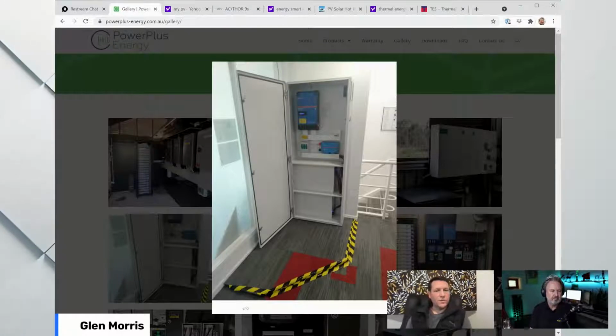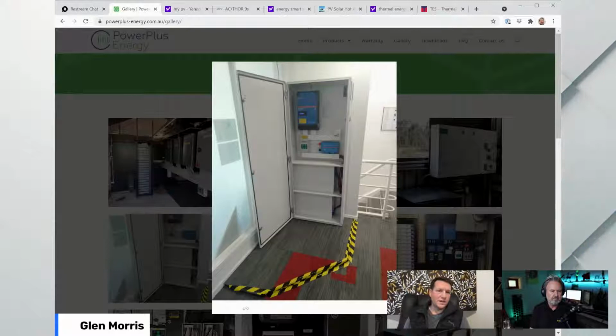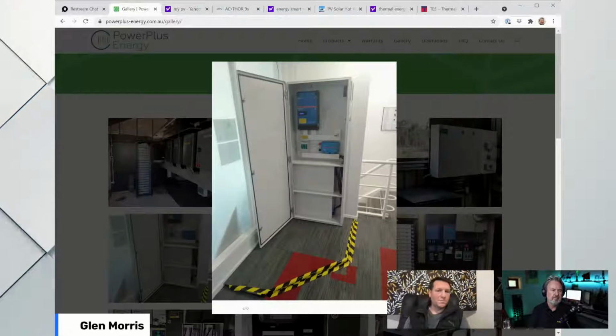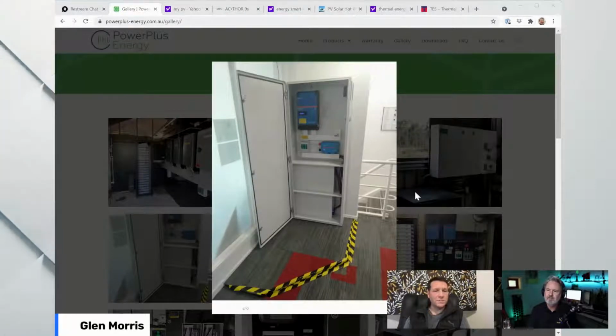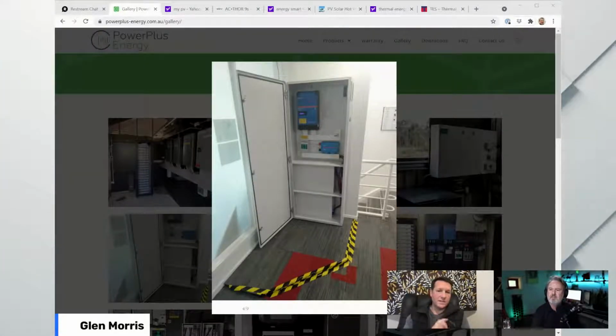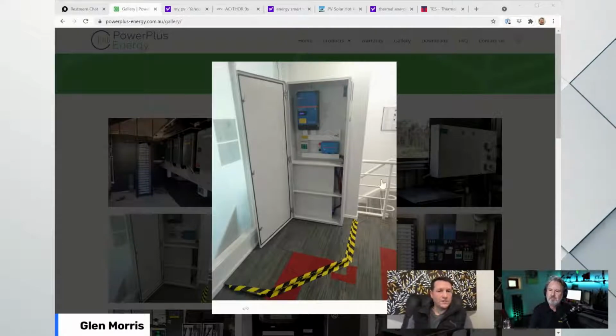I mentioned before that these cabinets used to come with a kit of equipment: a fan, a thermostat, a fan and a vent in the top section, and we were using the Victron Lynx for our DC bus bar and a Noark breaker, 250 amp breaker. But now we've moved to our bus bar system on this cabinet, with the bus bar and DC isolator mounted in the lower section with the batteries, making it an easier and faster installation.